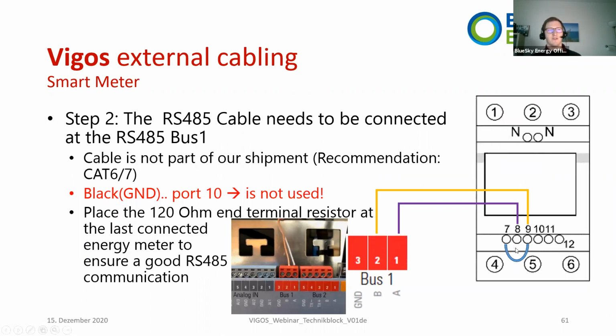The communication needs to be done like this. On the energy meter, you have the pins 9 and 8, and these need to be connected to the EMS Bus 1, pin 1 and 2. This is a 3-port orange plug, which you can also remove, and then connect your cables. I recommend a Cat 6 or 7, a standard communication cable, to do that communication cabling.